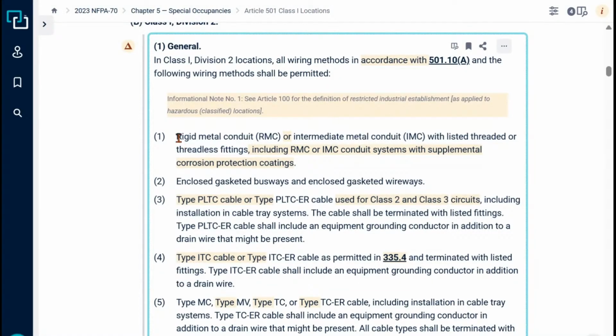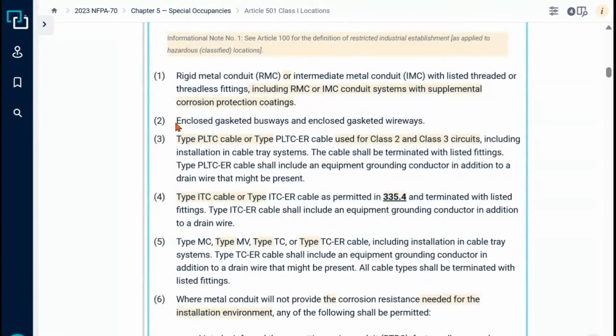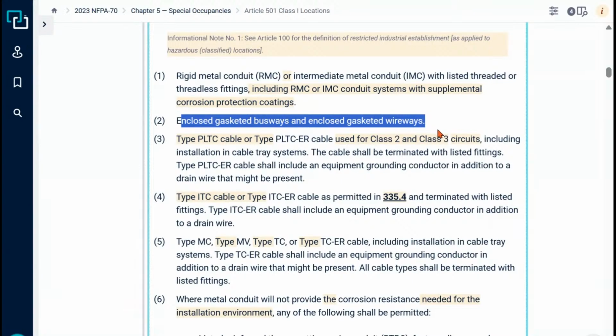It says rigid metal conduit. So obviously that's okay in Class 1 Division 1. It should be okay in Division 2, right? Intermediate, that's okay, right? Threaded entry, no problem. Enclosed gasketed busways and enclosed gasketed wireways. That was different. That wasn't in Class 1 Division 1. So a few more types of methods.